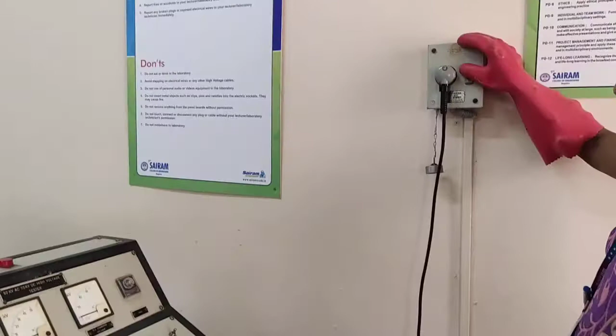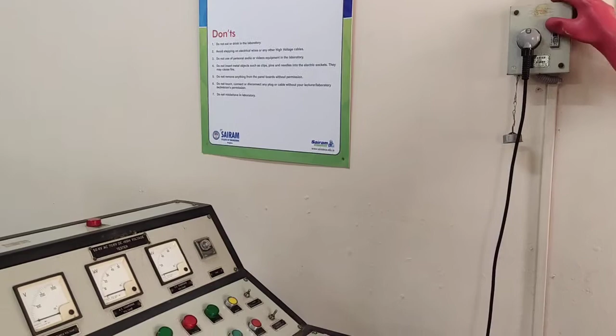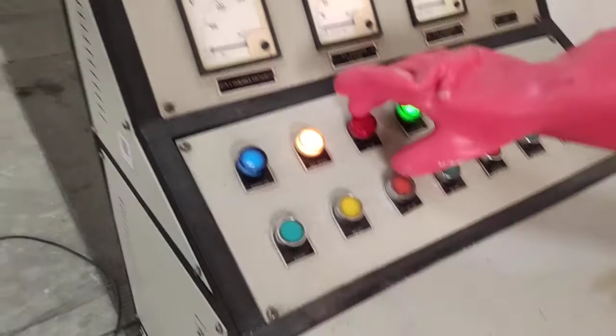So now I wear the rubber gloves, switch on the main power supply. Then press the mains on push button. Wait till the unit ready lamp is glowing. Now the unit ready lamp is glowing. Then press the HT on push button. Now press the increase voltage push button.